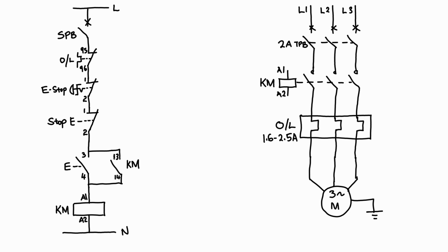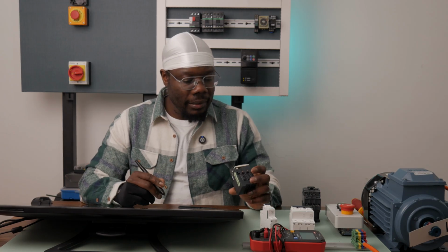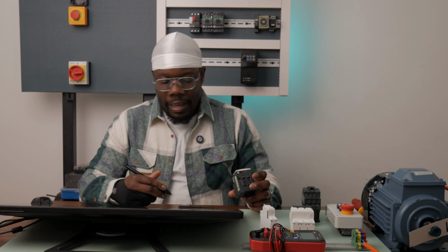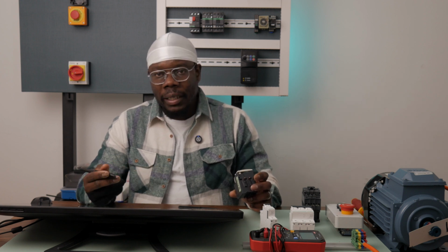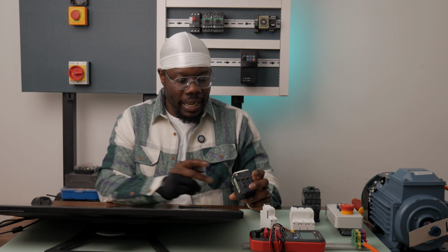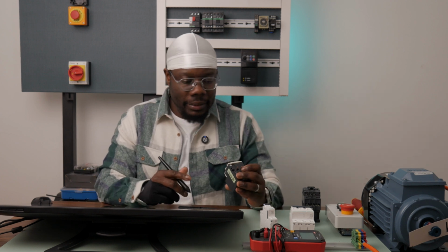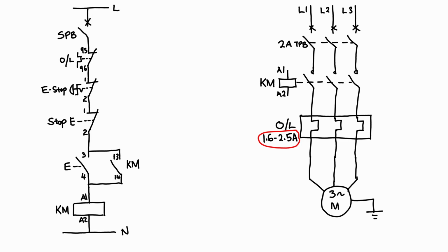For more detailed schematics, sometimes they will indicate the range of tripping currents of your overload relay, like this one that I have here, which ranges from 1.6 amps to 2.5. It's your choice if you want to include this detail. So this is the basic power circuit of a direct online starter and the basic control circuit. These are the circuits that we're going to wire up to run our electric motor.